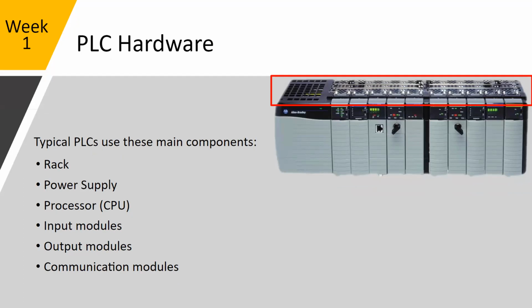So this here is your power supply. The electrician in the panel will wire 120, 24 volts to this unit. It'll power up the whole rack and it'll bring these cards online. In this particular rack, and this is possible, you actually have two processors. For Allen Bradley, you can identify them because they're the ones with this key on the front of them.